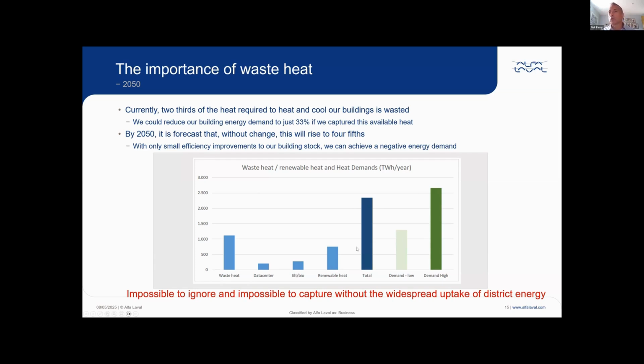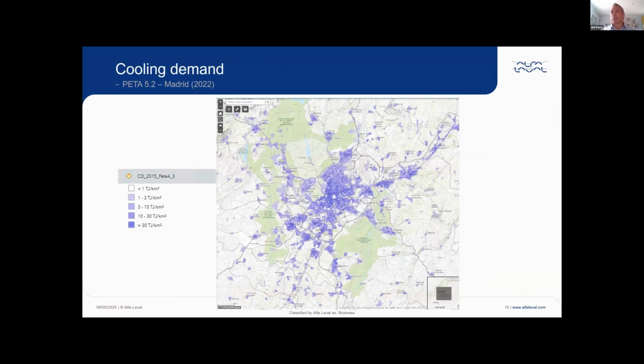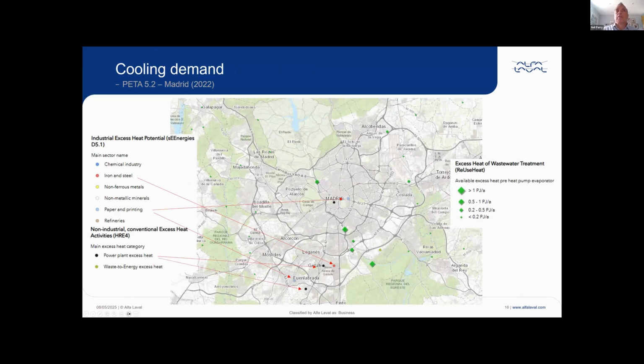I won't go in this presentation into where that heat is, but it's important to note that this was available waste heat, and the definition of that was waste heat that is easy to capture. So I've hinted at why that's important, because once you have waste heat, you can use absorption heat pumps and absorption chillers to produce cooling. Now, this is a map of Madrid, so I'm sticking with the Spain theme. This is PETA 5.2, and this shows the cooling demands in and around Madrid, and the colors represent the amount of cooling required. If we overlay over that available waste heat, we end up with lots and lots of arrows all pointing in various places. We can see there is iron and steel production down here. We have paper and printing in two different places, a lot of waste heat from that. We have power plants with excessive heat in different places.